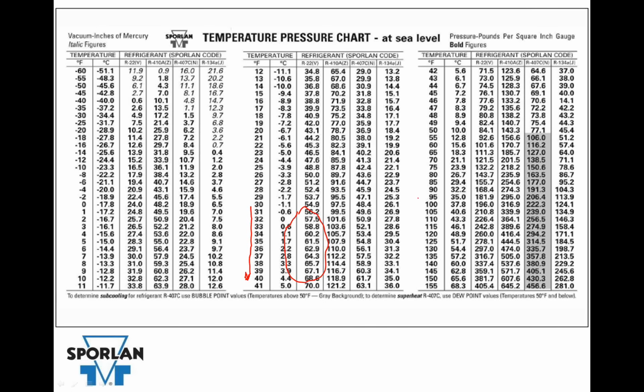Over here, though, when we get over to this side of the equation, if we're calculating subcooling, we're at 100, 105, 110. Look at these pressures, 196 to 210. So we have 14 pounds of difference here. Well, what's the technician left to do here? Because if you're going to remember, Energy Star told us plus or minus 3 degrees. Well, if I've got a gauge that's plus or minus 8 to 10 pounds, and I've got a temperature pressure chart where I've got to take a guess or interpolate where that lands, there's not a whole heck of a lot of chance of me ever getting that subcooling within the 3 degrees that the manufacturers are requiring.